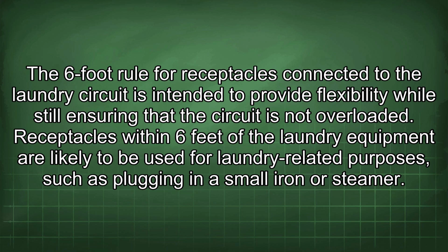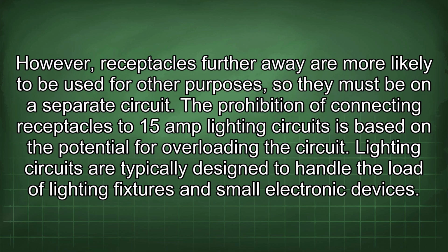Receptacles within 6 feet of the laundry equipment are likely to be used for laundry-related purposes, such as plugging in a small iron or steamer. However, receptacles further away are more likely to be used for other purposes, so they must be on a separate circuit. The prohibition of connecting receptacles to 15-amp lighting circuits is based on the potential for overloading the circuit.